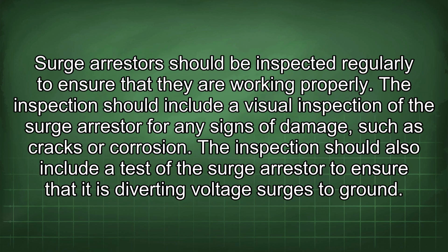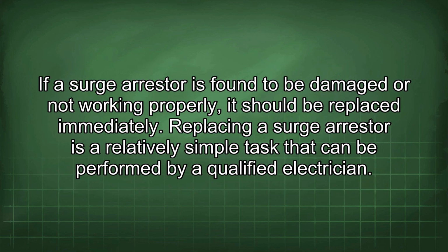Surge arrestors should be inspected regularly to ensure that they are working properly. The inspection should include a visual inspection of the surge arrestor for any signs of damage, such as cracks or corrosion. The inspection should also include a test of the surge arrestor to ensure that it is diverting voltage surges to ground. If a surge arrestor is found to be damaged or not working properly, it should be replaced immediately. Replacing a surge arrestor is a relatively simple task that can be performed by a qualified electrician.